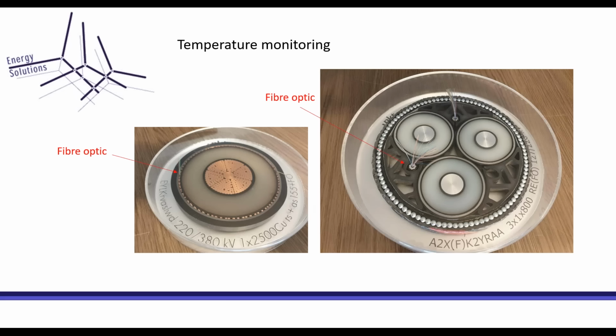So how does it look in practice? These are two examples of underground power cables. On the left one you see a single core cable with the fiber optic integrated under the metal sheath. You cannot place the fiber optic in the core because that's just not possible. But in the end, what you want to know is the temperature in the conductor, because that's the limiting factor in the cable. So the way you do this is you use the thermal model to calculate this temperature back, and it's not a fixed temperature difference between the fiber optic and the conductor; it varies with the load. So that's why it's important to have a thermal model to do these calculations.